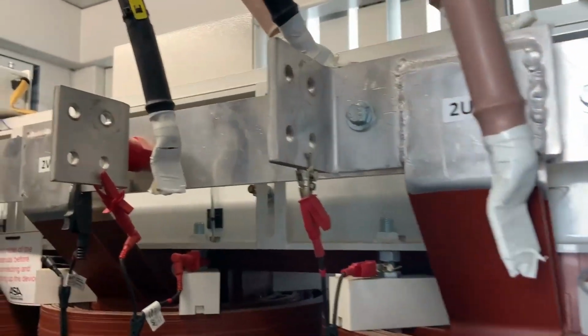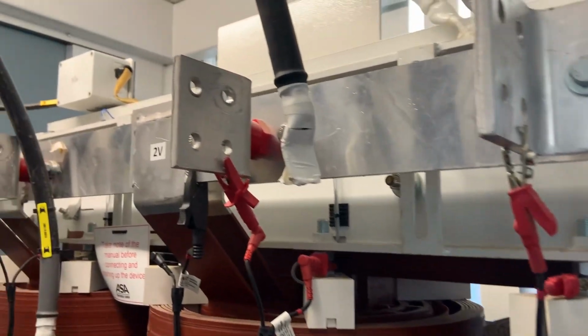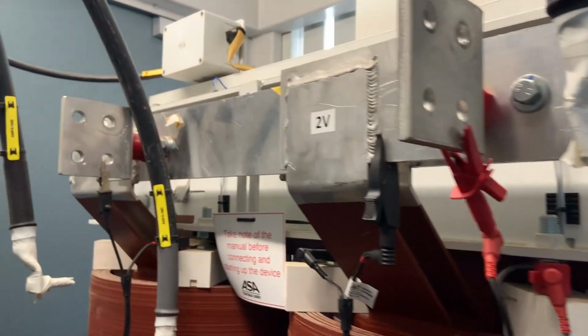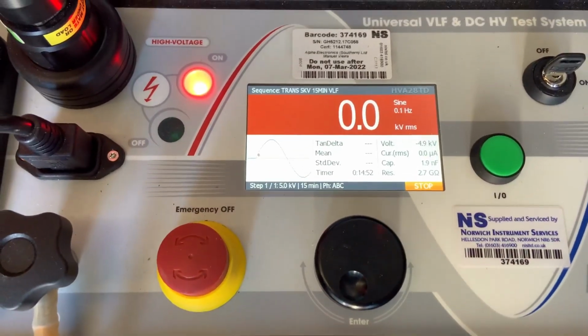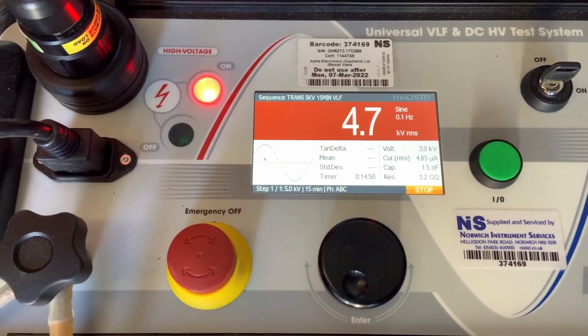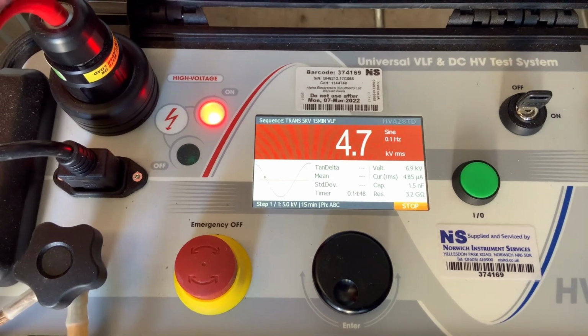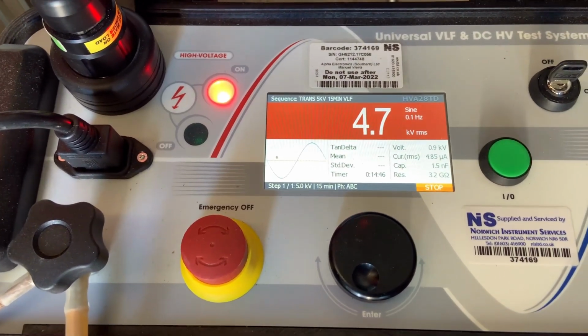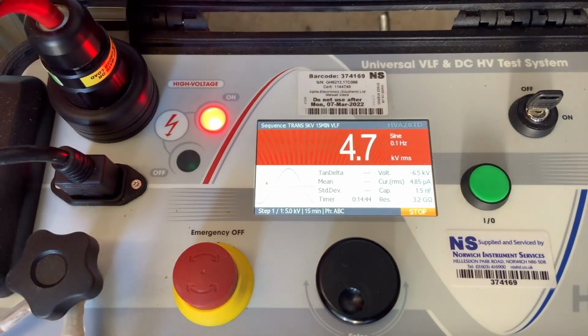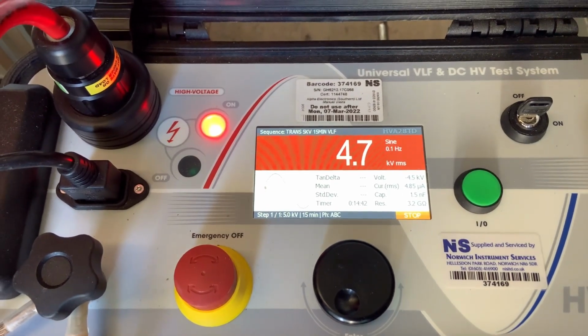And the final test, test 3, is we connect each of the LV windings down to earth. We then apply 5 kV VLF onto the high voltage side. So this is checking the resistance between the HV and the LV windings.